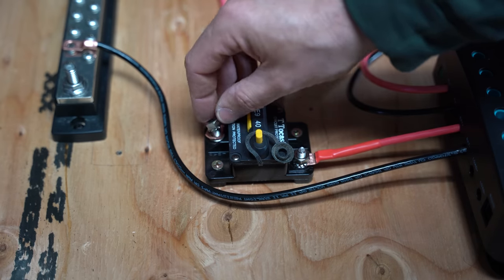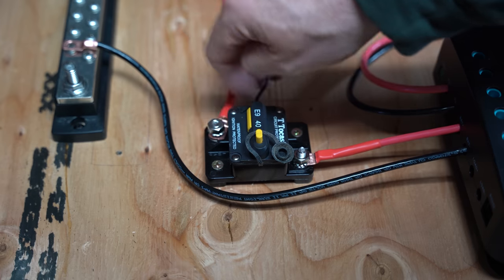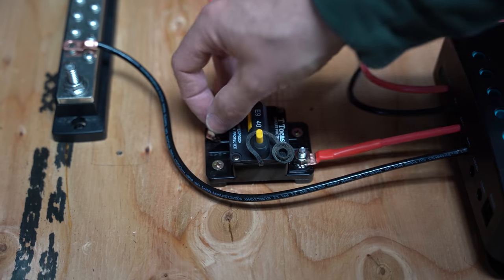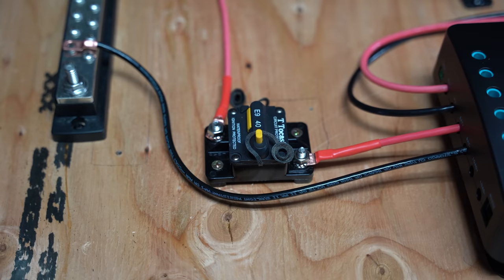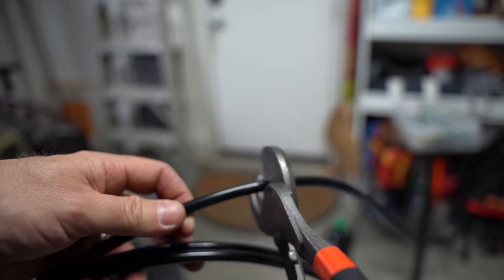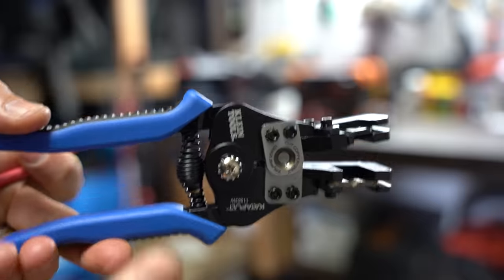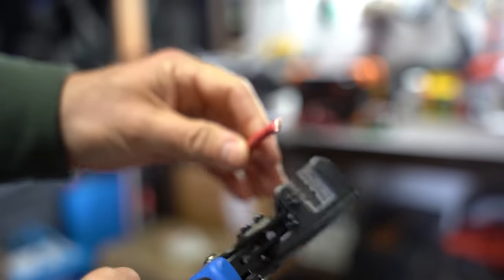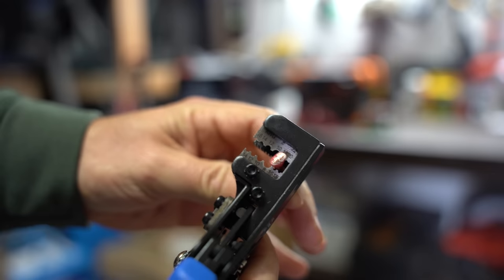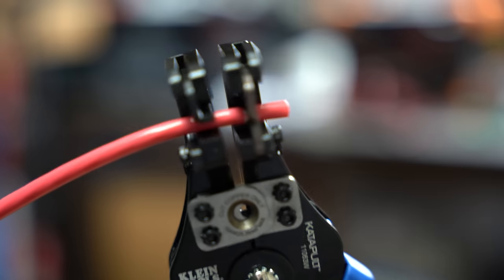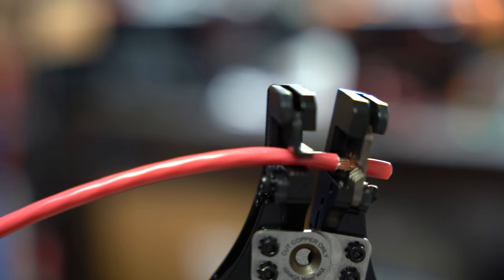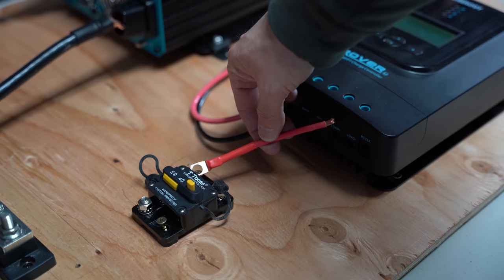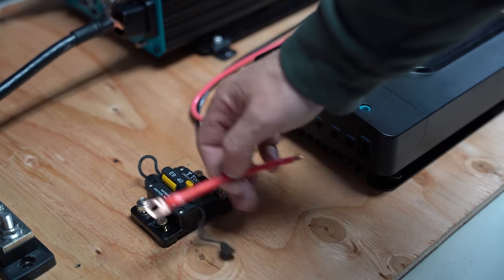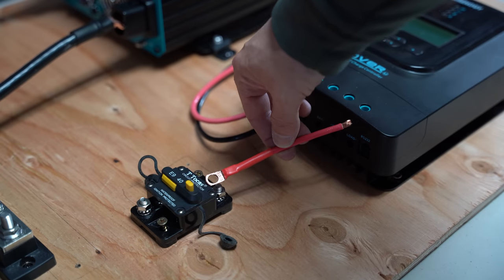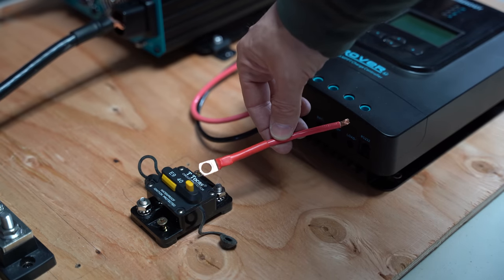The tools needed for smaller cables are different. To begin with, we'll determine the distance from the charge controller to the 40 amp fuse. Measuring that distance, we'll then cut our wire with the tool shown here. To strip the insulation off the ends of this 8 gauge or smaller wire, there's a tool that you can use as shown here. It cuts the insulation perfectly, and you can then strip the insulation off the end. On one end of the wire, we're not going to need a cable lug, as we'll plug this directly into the charge controller, and then on the other end, we're going to put on a cable lug.